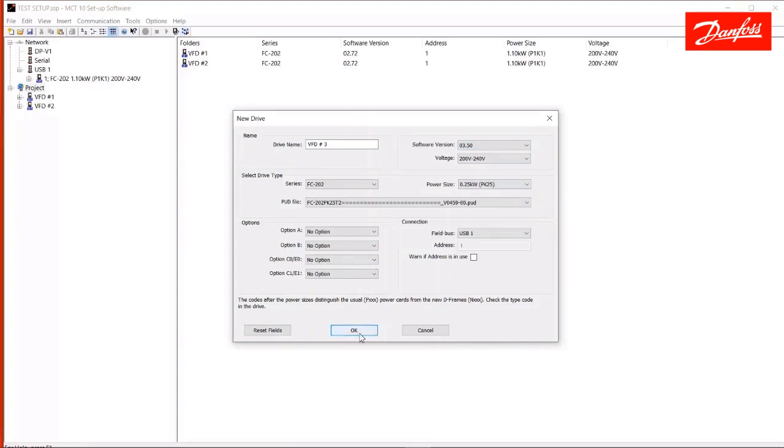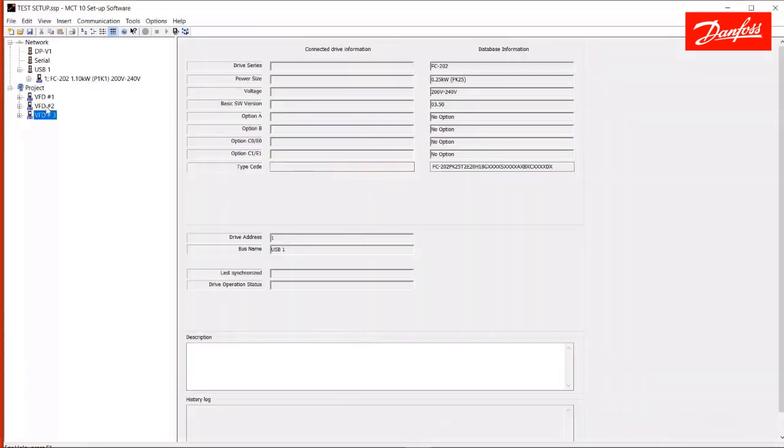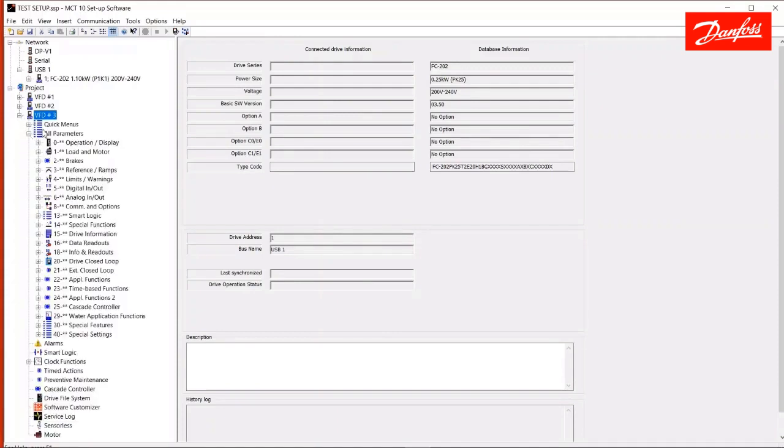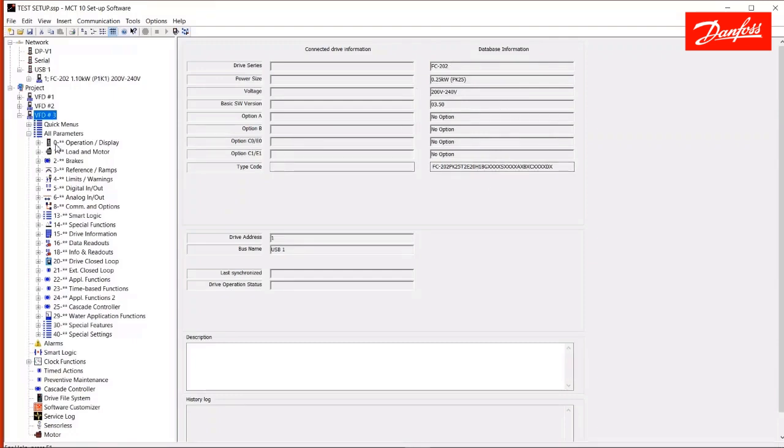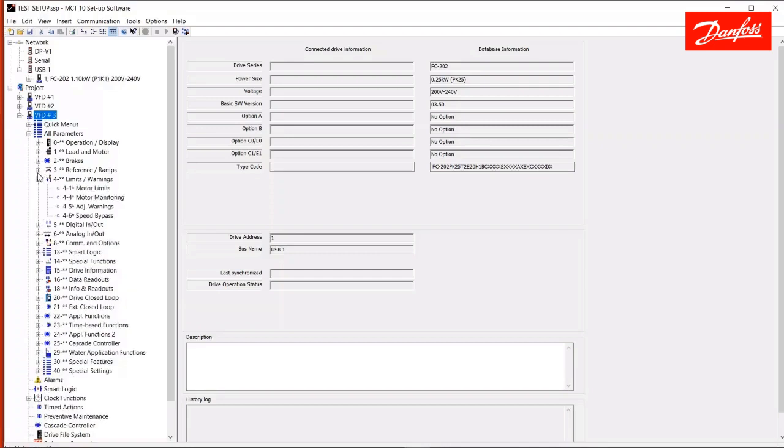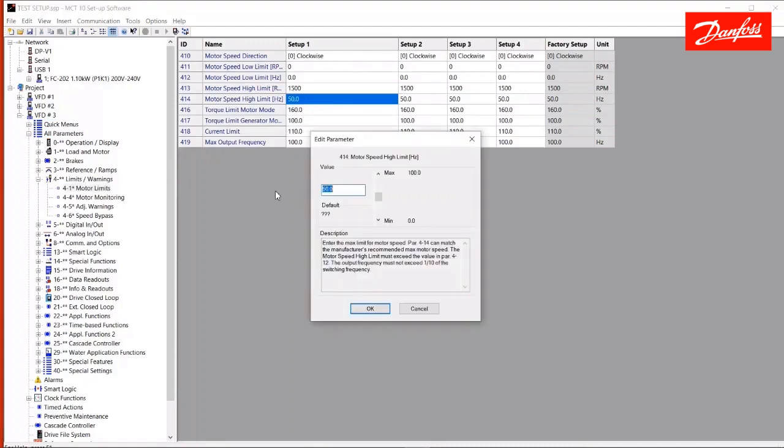So, I'm going to go ahead and say okay here. And now we'll see I have VFD number three. And this is a complete default setup of a FC-202. This particular drive is .25 kilowatts, 200 to 240 volts. So, there are some differences here between this and the live drive. And I'll show you what happens when there are differences, and I go to write this information. So, normally the purpose of creating this generic project drive is so someone can program the drive at their own leisure before getting on site. So, you can go through and make all the changes that you need to to this drive and essentially set up the complete setup.